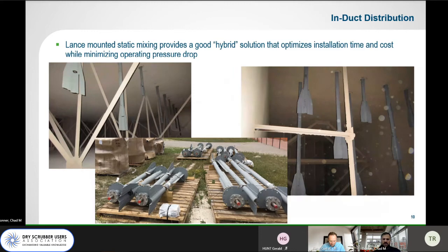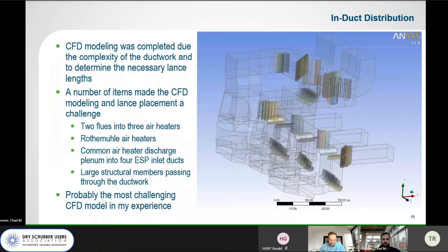Here's just a typical installation of the mixing lances that we use at Duke. They create localized turbulence to get the hydrated lime mixed up quicker in the flue gas. So after seeing that, we initiated a CFD model due to the complexity of the ductwork at Crystal River. A number of items made this modeling and the overall distribution a challenge.